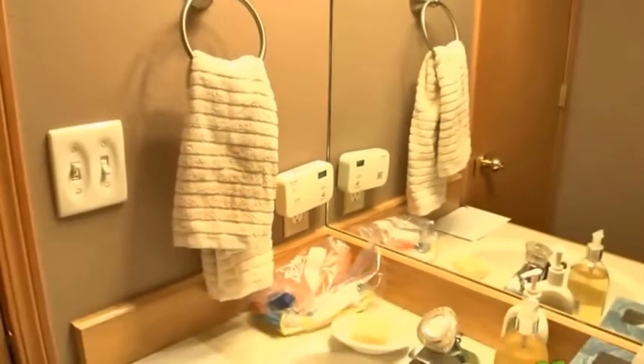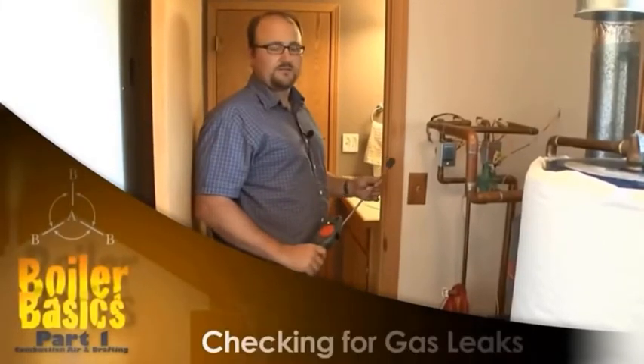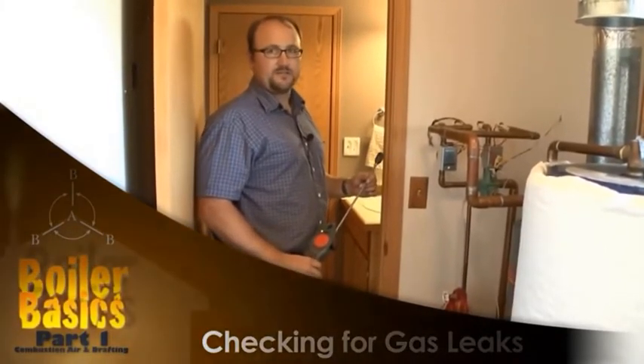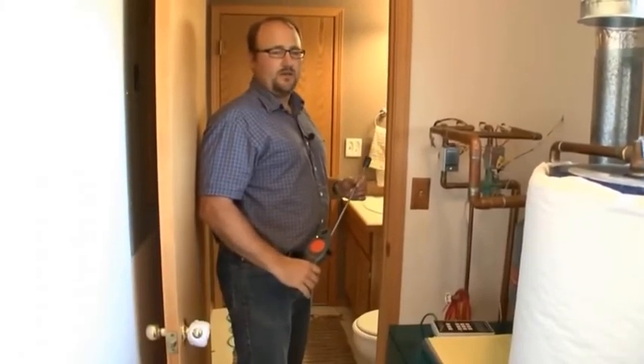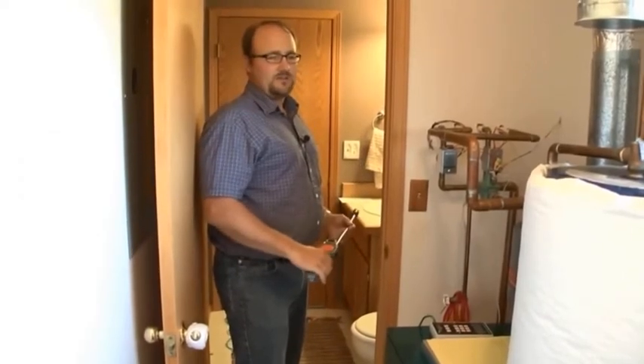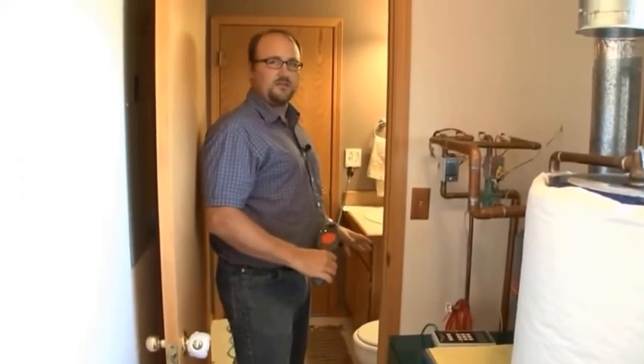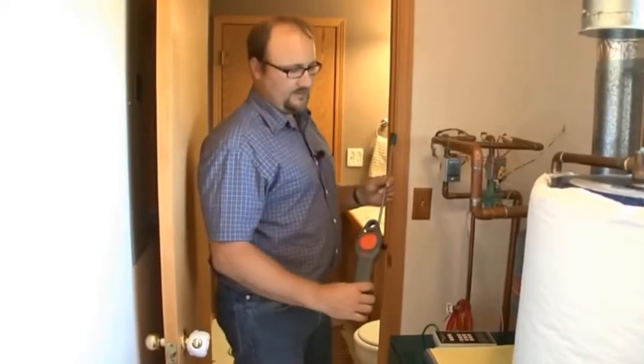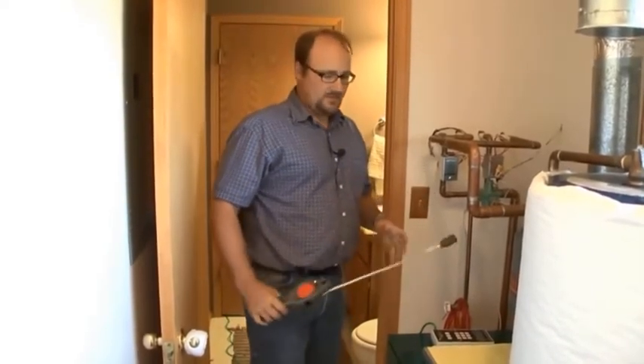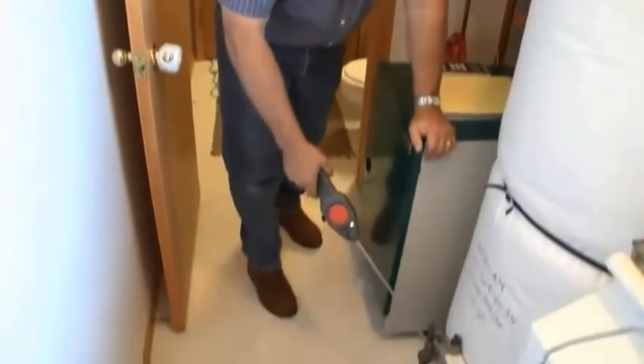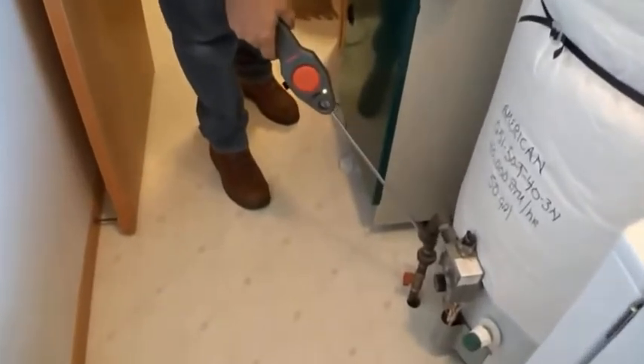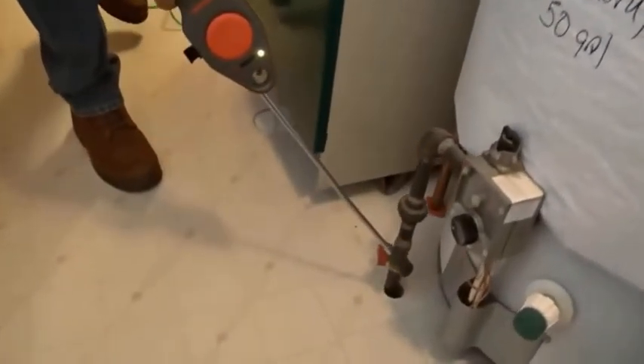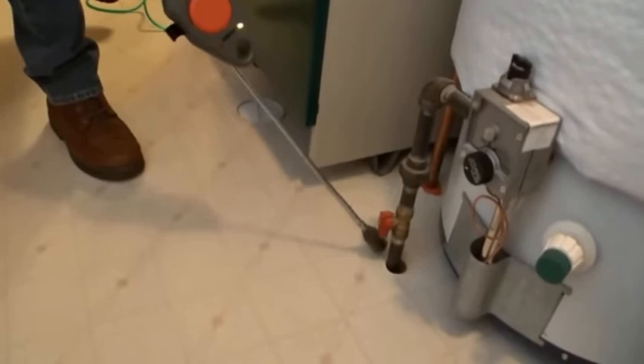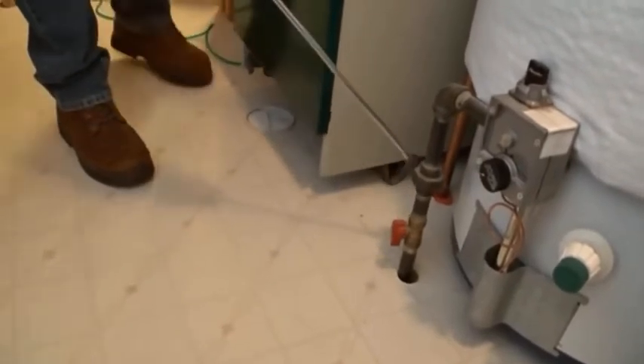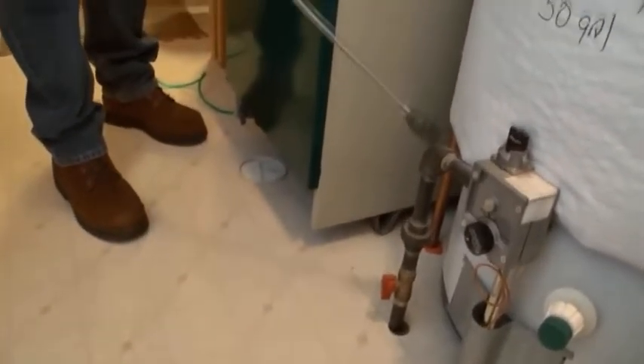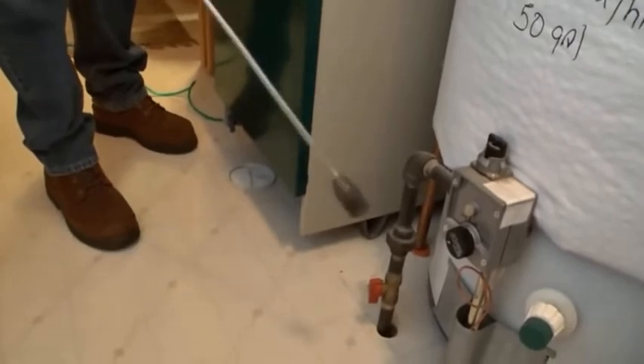Prior to doing any diagnostics work, what I want to do is check for gas leaks. I go down into the crawl space in this house, use this leak detector, check for gas leaks down there, and check for gas leaks at the appliance. I basically do the same technique all the way through all the gas lines and make sure I don't have any leaks. If I do have leaks, I need to fix them before I continue with any of my diagnostics.